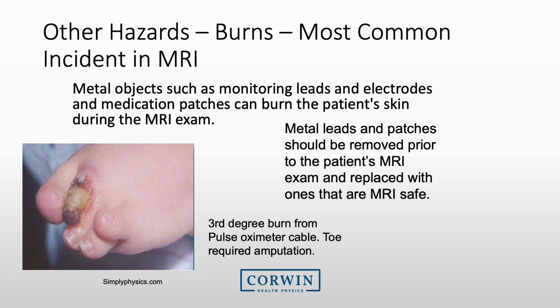Patient heating in general is a common concern, but in addition to general patient heating, we need to worry about specific burns caused by items left on the patient. MRI-associated burns constitute the most frequently reported injury in MRI. Metal objects can cause burns on the patient's skin when the RF field interacts with them. All metal leads and patches should be removed prior to the patient entering the MRI room.